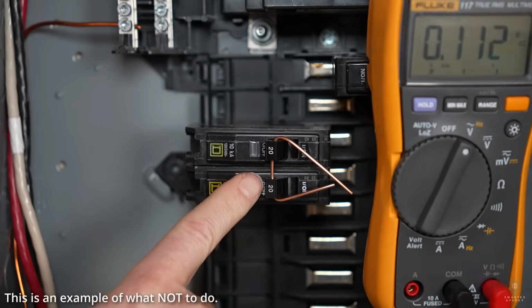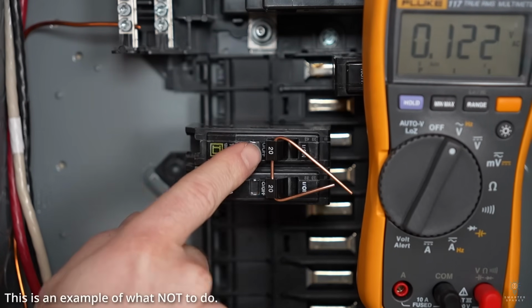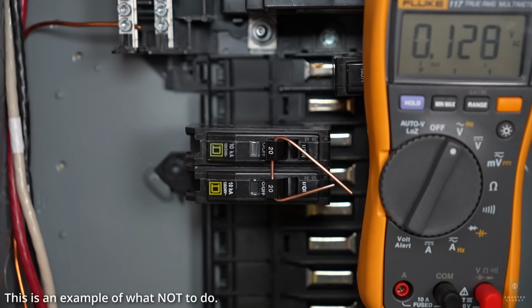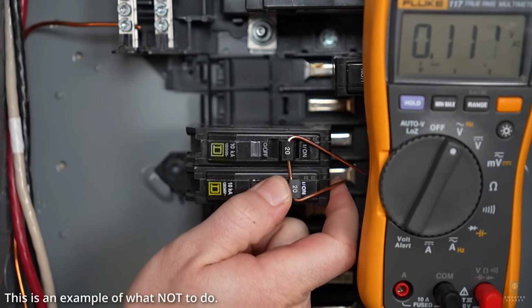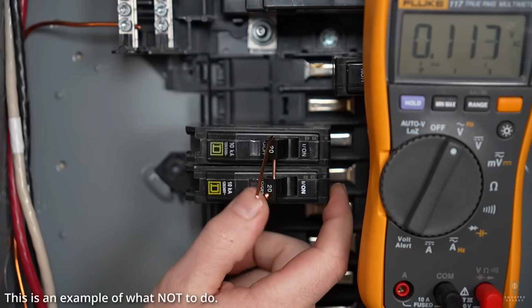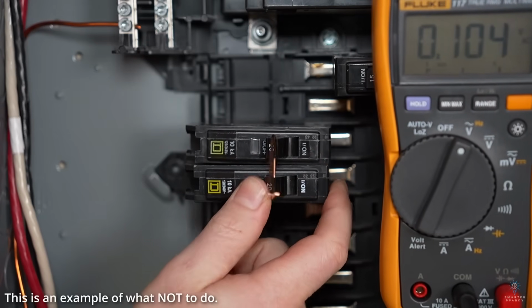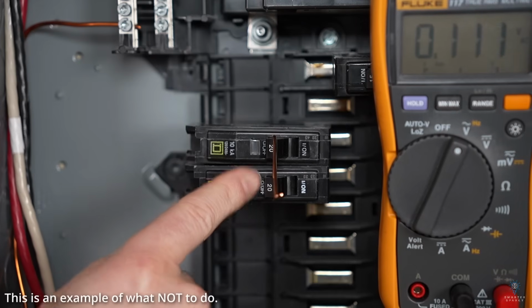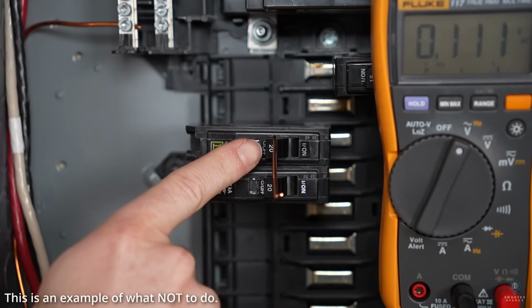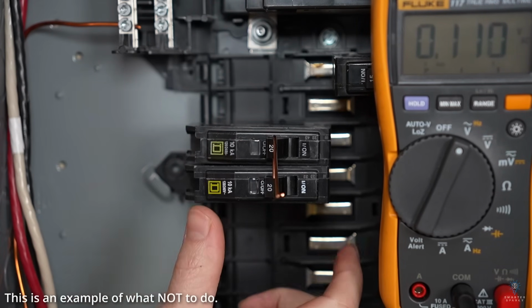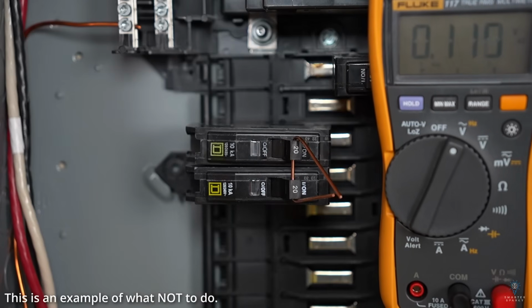Because these circuit breakers have holes in them, right? So now both of these trip mechanisms are connected together, right? Well, let's test that. If I flip this bottom one on, why isn't it going on? That's because this wire is so flexible, it's not able to turn this top one on completely. Now, if I force them both into the on position, sure, they stay.